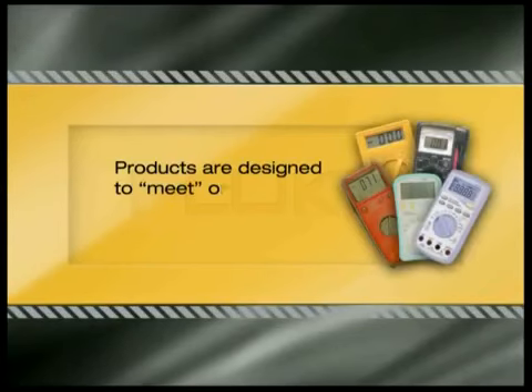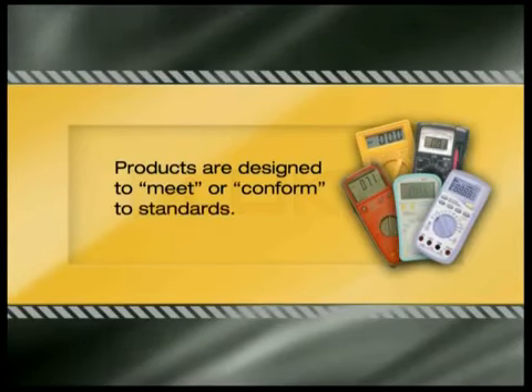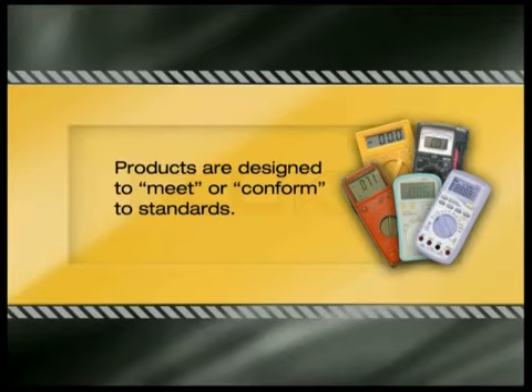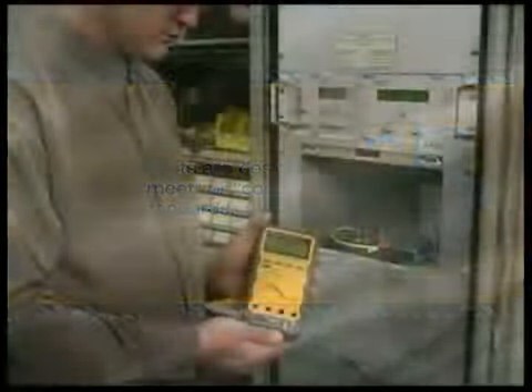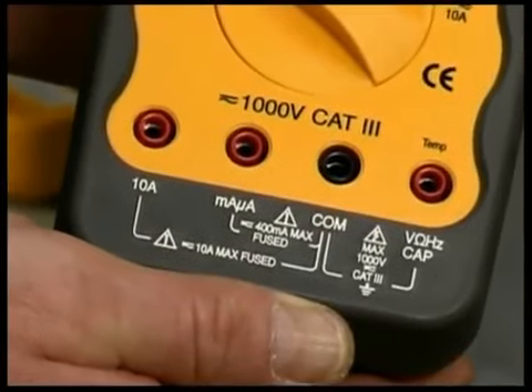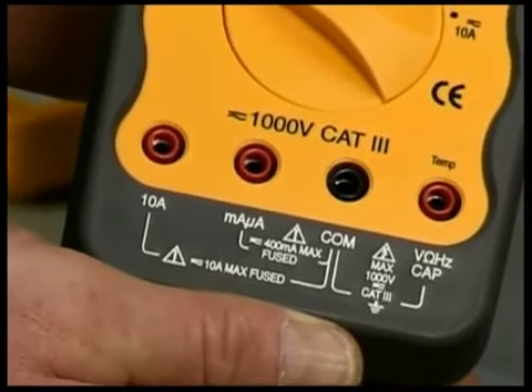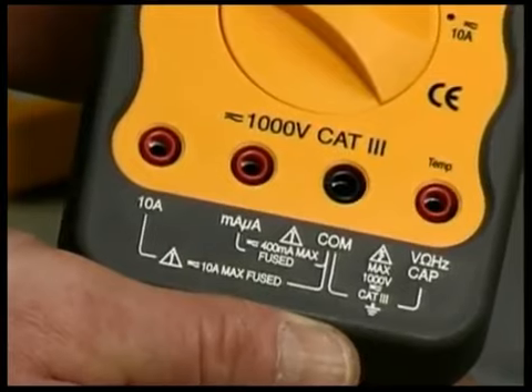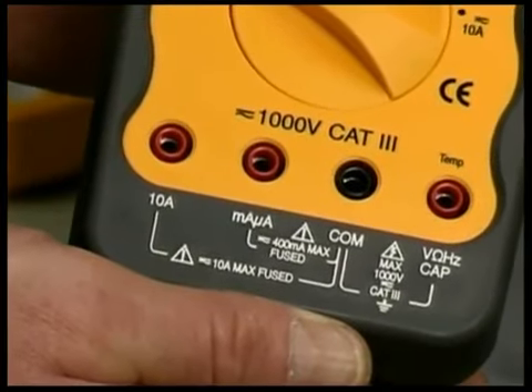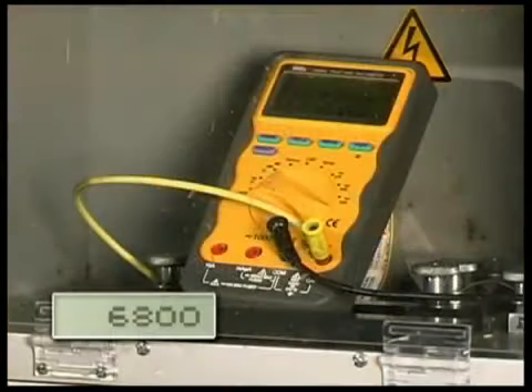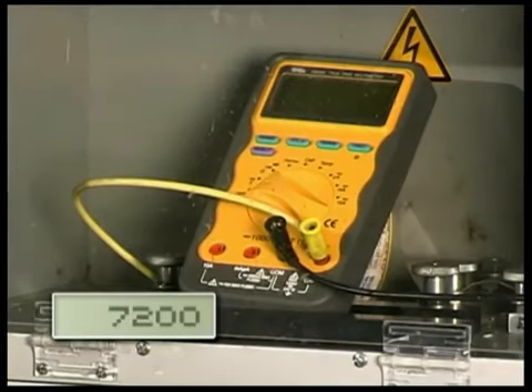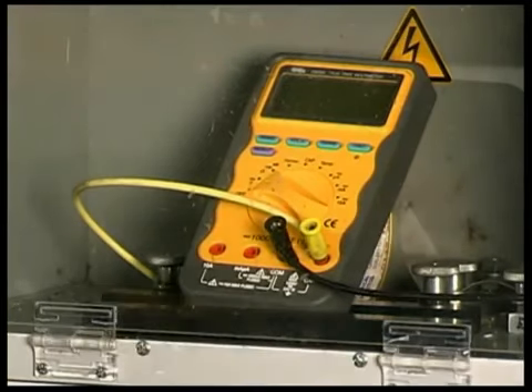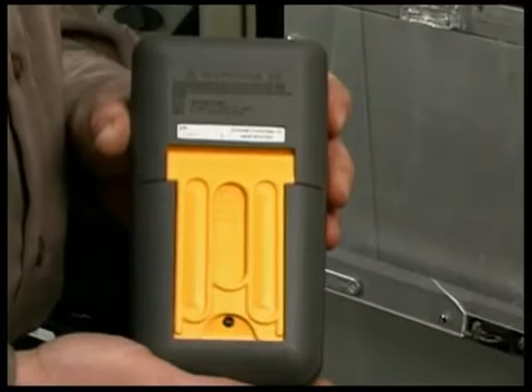Some manufacturers state that their products are designed to meet or conform to standards. But not every meter or tester that makes that claim will pass the test. Here's what happened when a meter marked 1000 volts Cat 3 was actually tested. It should withstand a minimum of 20 transients of 8 kilovolts. But this meter failed twice before reaching the 8 kilovolt minimum level. On a real power circuit, these results could have been disastrous.